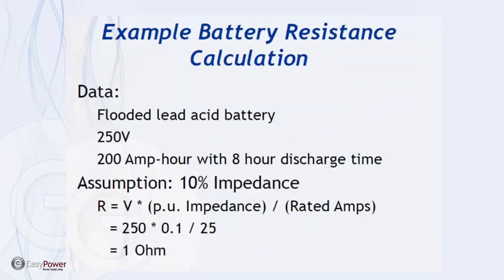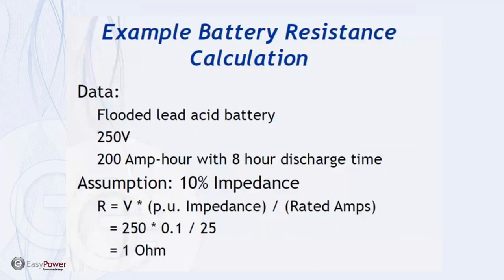So if we're going to calculate a typical battery resistance, say for a flooded lead acid battery at 250 volts, if it's rated at 200 amp hour with an 8 hour discharge time, and if we assume 10% impedance from that lookup table, we show that the resistance for the battery will be the voltage divided by the rated amps and a per unit impedance base. And we get roughly 1 ohm internal resistance for a lead acid battery under these conditions.